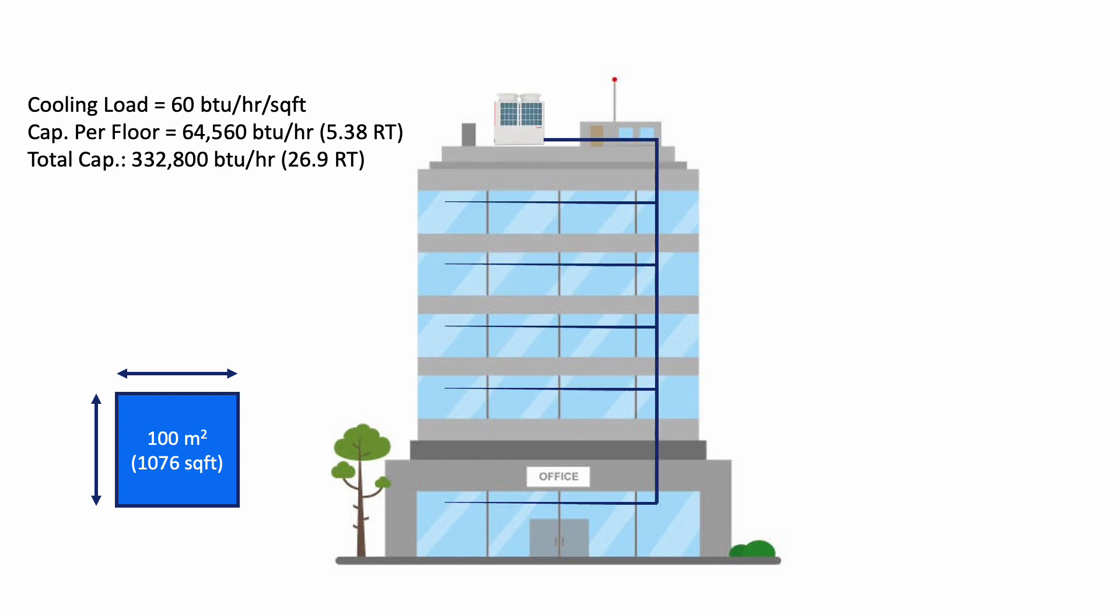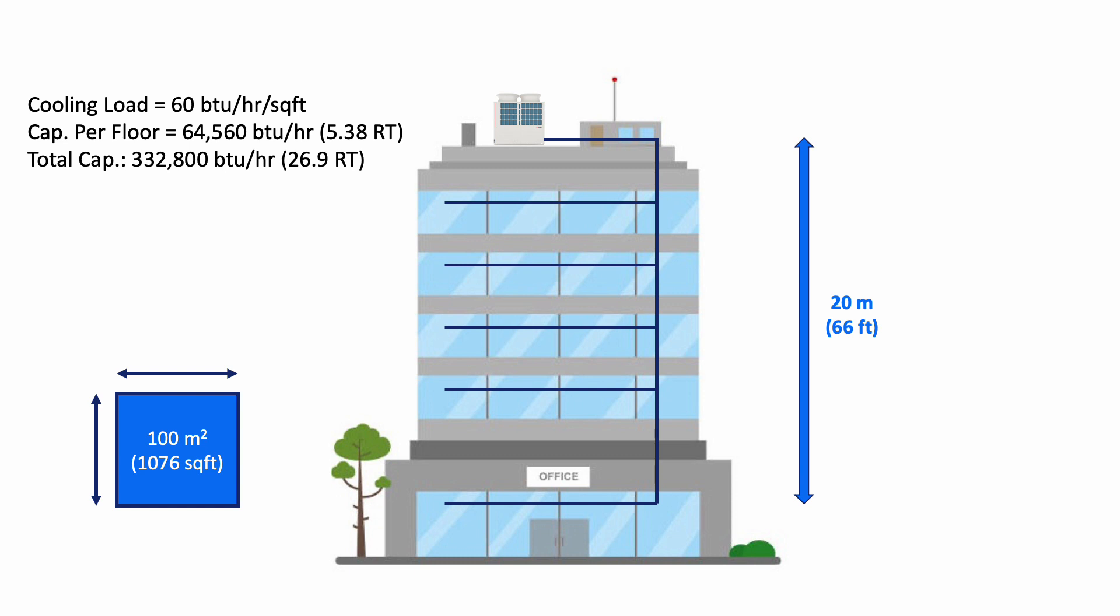You get rid of all those outdoor units, then you can put one unit on the roof. Then the refrigerant pipe, you just run one pair and go down. So the space is really minimal for VRF system. This is the advantage of this VRF system. But there's a small limitation for VRF system, the vertical height cannot exceed too much. For example, in this example, you measure from the lowest indoor unit up until the outdoor unit, the vertical height distance is 20 meters. 20 meters for a VRF system is no problem at all because most VRF systems can go up to like 80 meters or some even 100 meters. You need to install some oil trap, but it can be done. The refrigerant and the lubrication oil can go back to the outdoor unit.